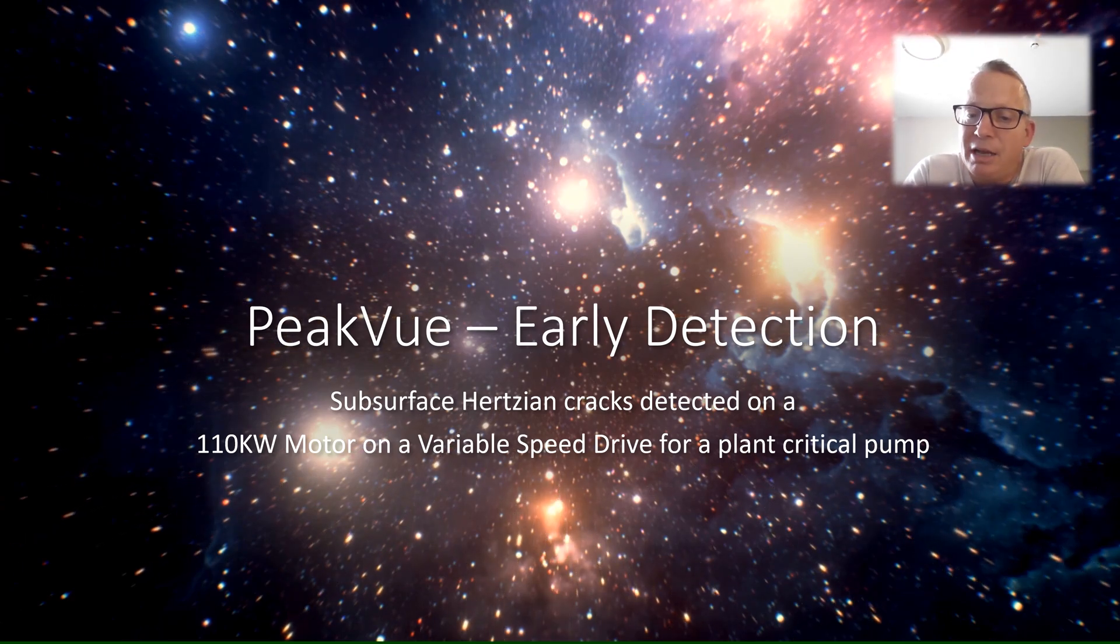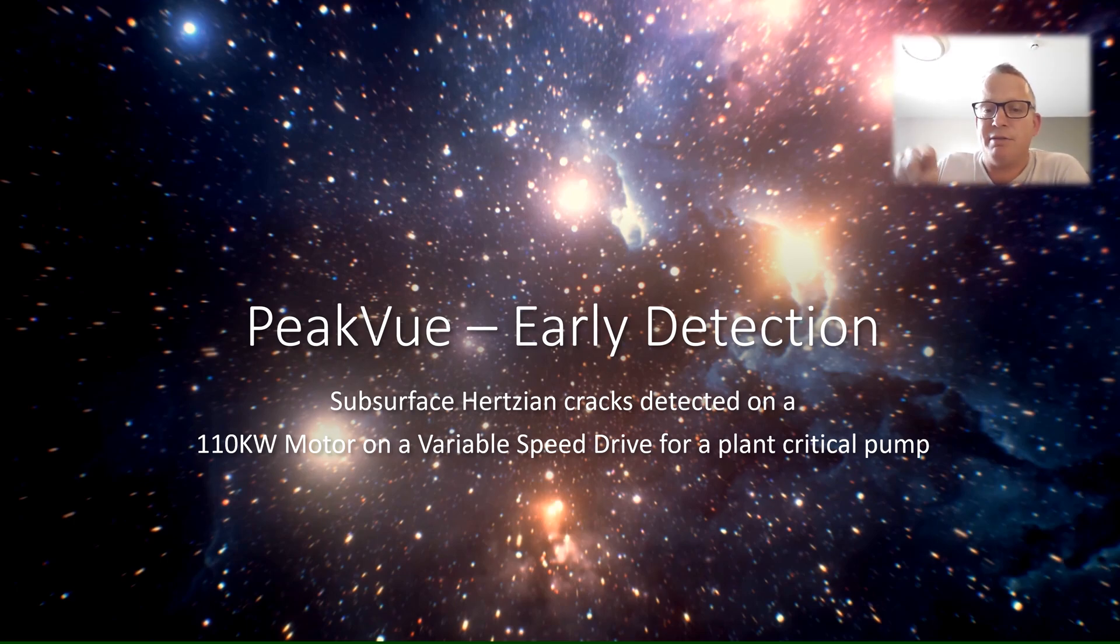We're looking at where we can pick up subsurface Hertzian cracks. So as the rolling element goes around, we've got a slight dent in the load zone, we get plastic deformation, where the grease also goes solid, stops the metal hitting the metal, but the ball bearing and the metal flex a little bit. So you get subsurface fatigue.